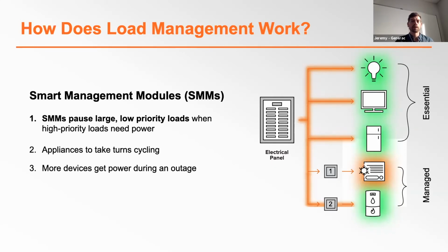So what happens is the inverter emits a frequency signal. The inverter's over here, by the way. We can't see this, but it's supplying the power, so it knows what's happening downstream. It's going to emit a frequency signal that is going to trigger the SMMs to pause, and it's going to repower in order of priority, so that the AC unit is going to power on first, and then after a brief recovery period, the rest of these managed circuits are going to come back on. So in this case, the hot water heater yields to the AC unit because the AC unit has a higher priority than the hot water heater.